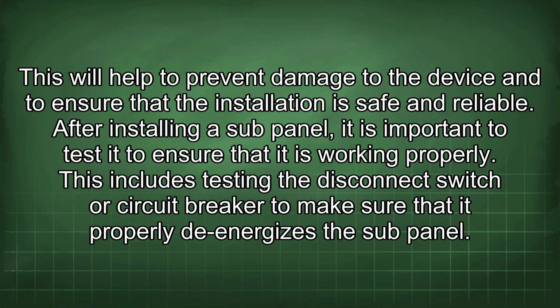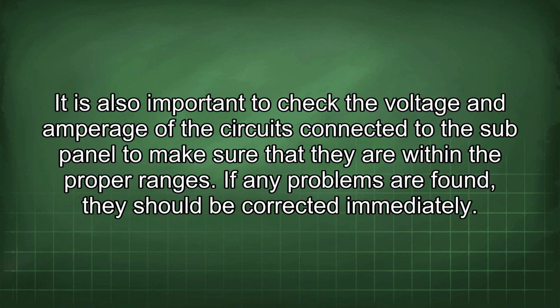After installing a sub-panel, it is important to test it to ensure that it is working properly. This includes testing the disconnect switch or circuit breaker to make sure that it properly de-energizes the sub-panel. It is also important to check the voltage and amperage of the circuits connected to the sub-panel to make sure that they are within the proper ranges. If any problems are found, they should be corrected immediately.